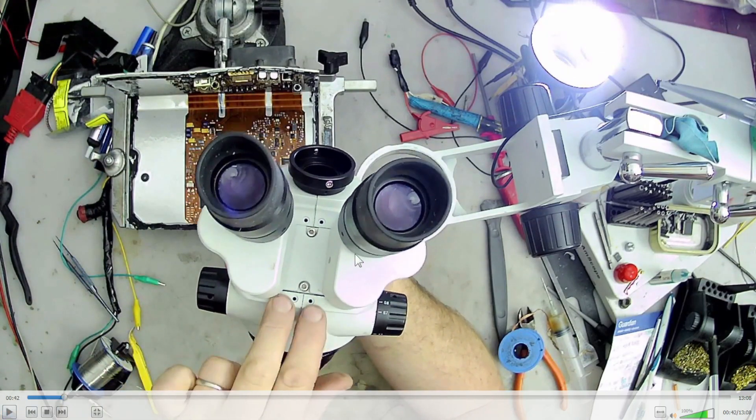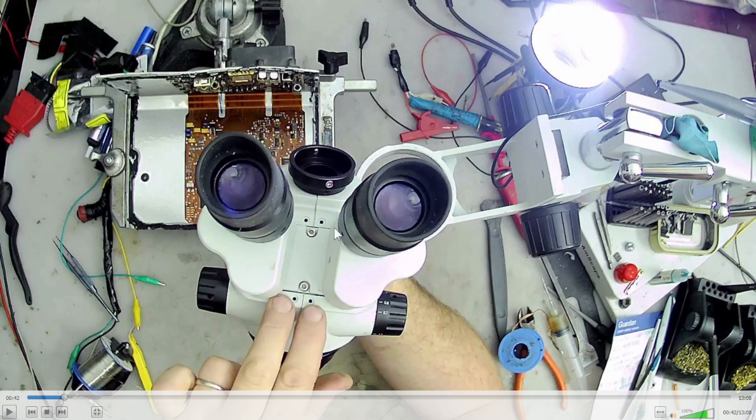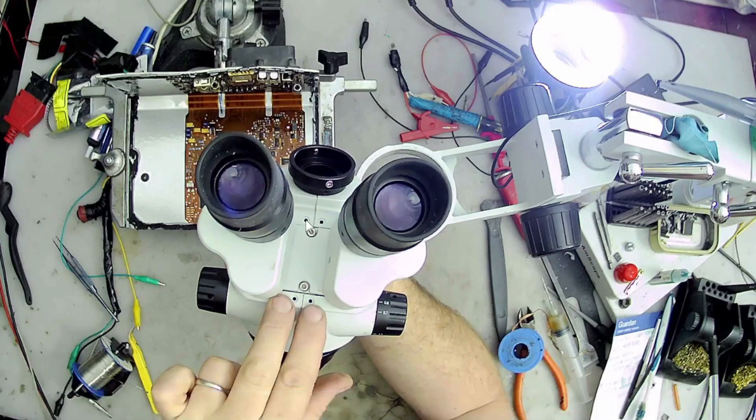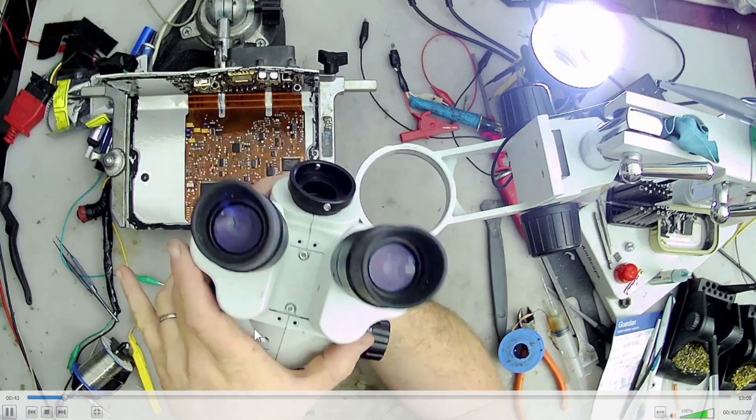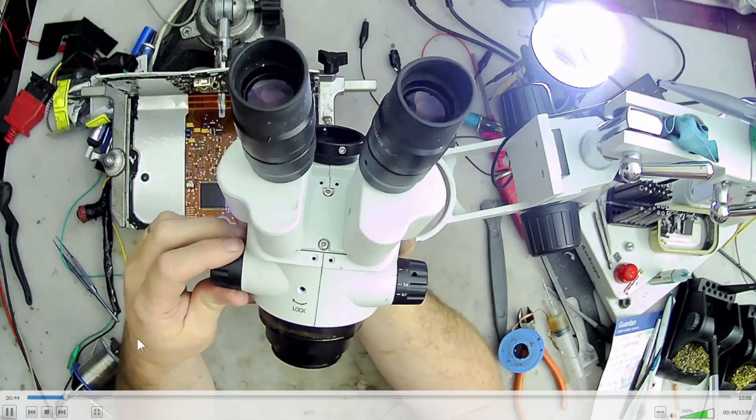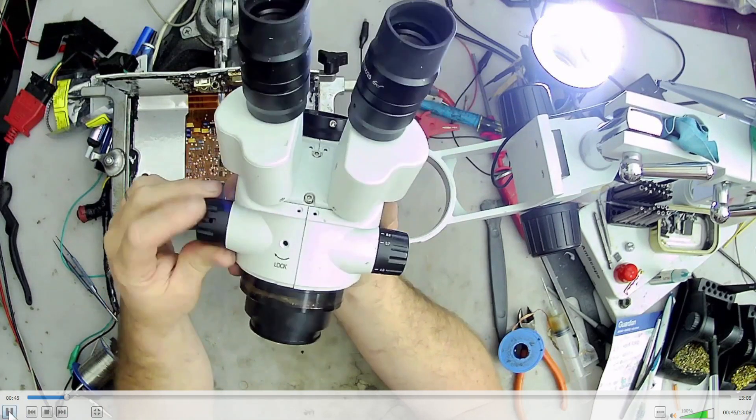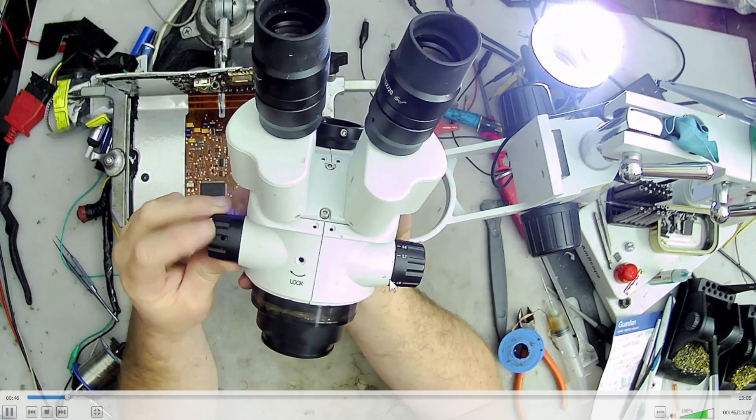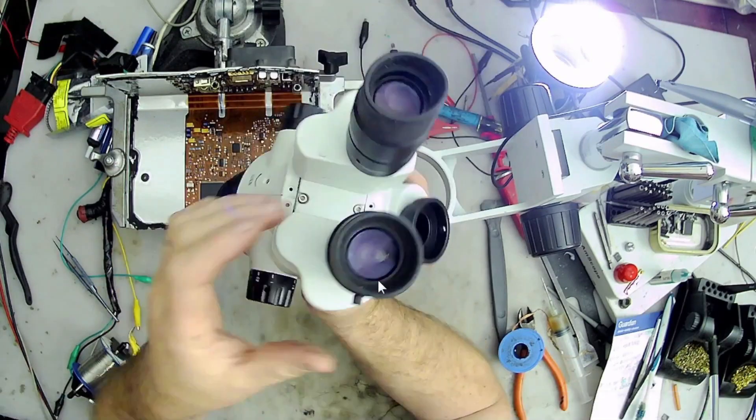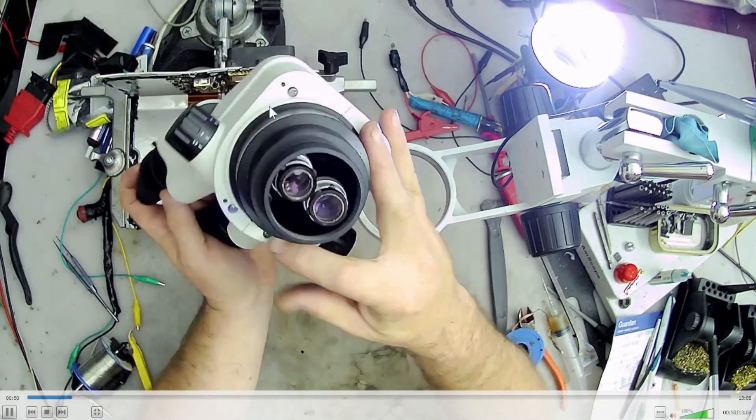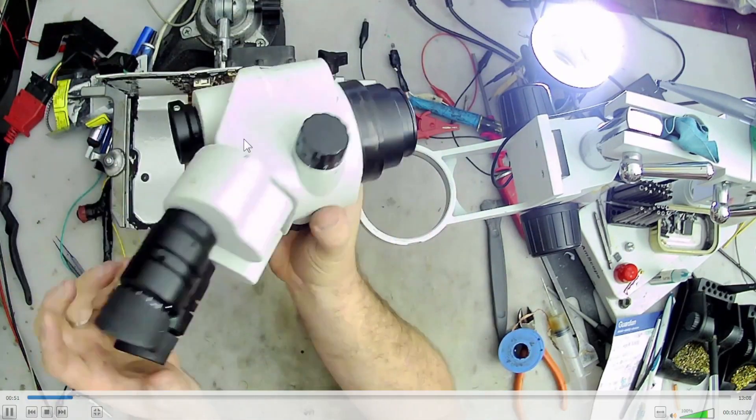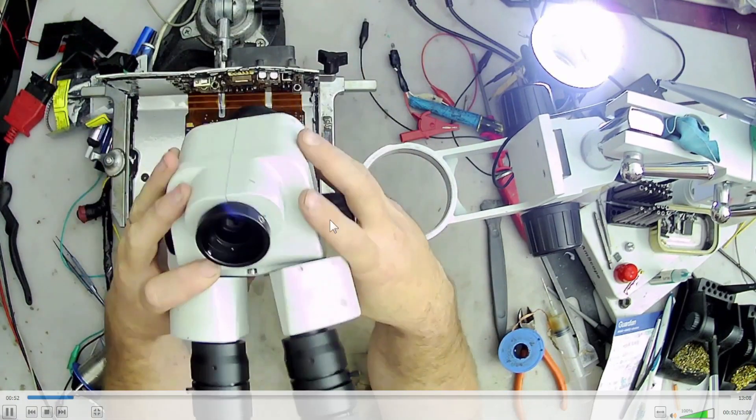Here I had already removed these and it was a mistake to do so. What these are is four screws here, but for each two there's a bar connecting them. And that's used to hold the case together. But what you should do is only take out one here and take out one here, so the bar doesn't fall and it's easier to put back together. And then for the magnification knobs there, they got two Allen screws for each one.